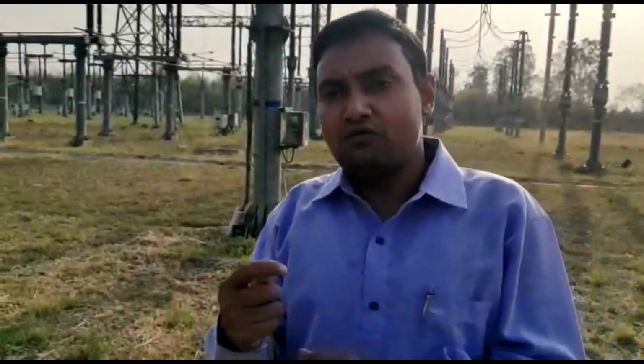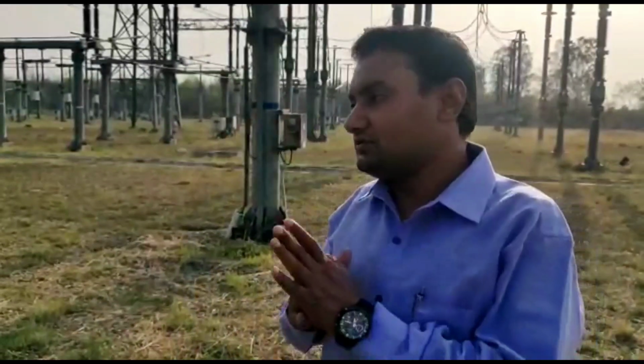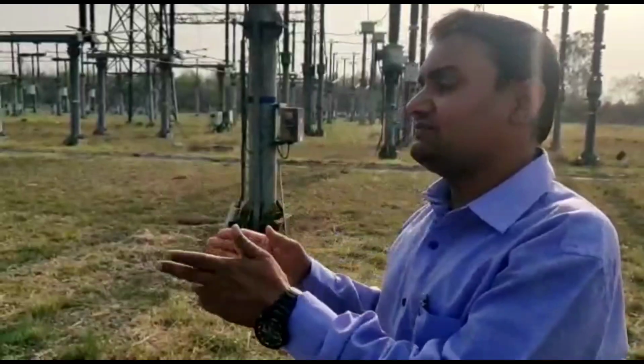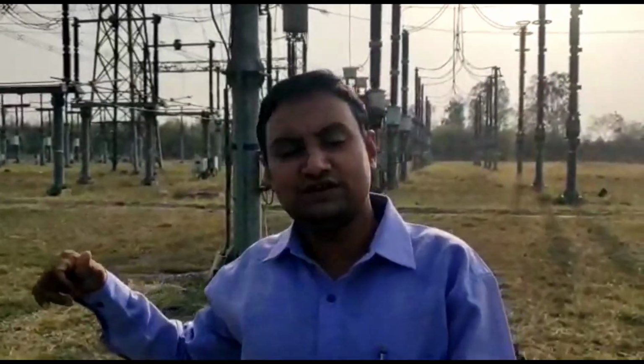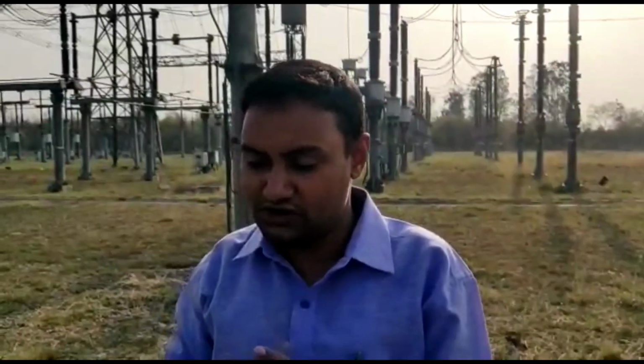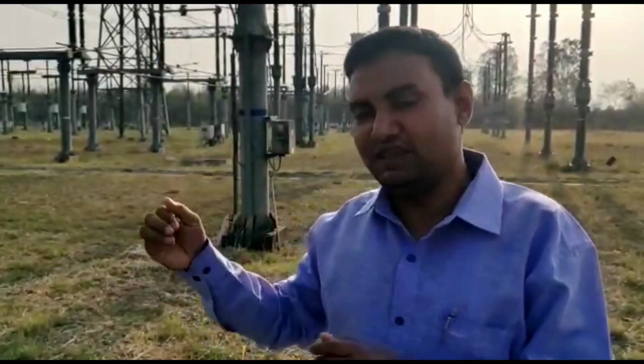One question that might be in your mind is, what happens when there is a phase-to-phase fault in these two phases themselves? In that case, there is a chance that your carrier signal might not be transferred to the other end due to severe attenuation. But again, that's not a big deal, because we are not using auto reclosure for phase-to-phase faults, and if there is a phase-to-phase fault, anyway you are issuing a 3-phase trip command, so that will not hamper your protection system and your protection scheme in the long run. Thank you.